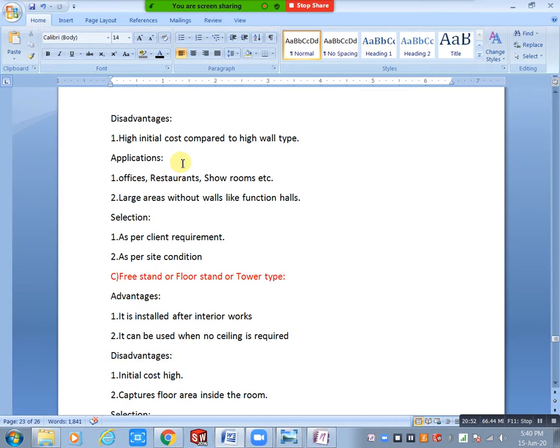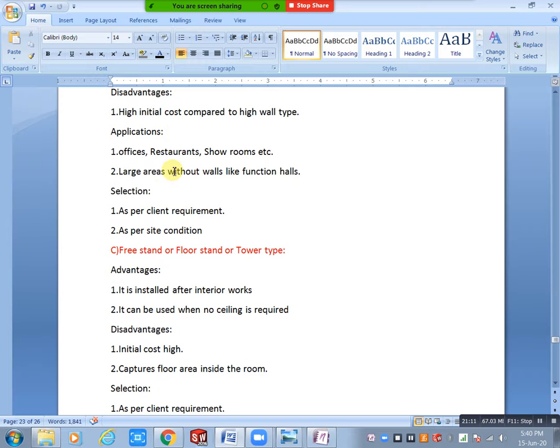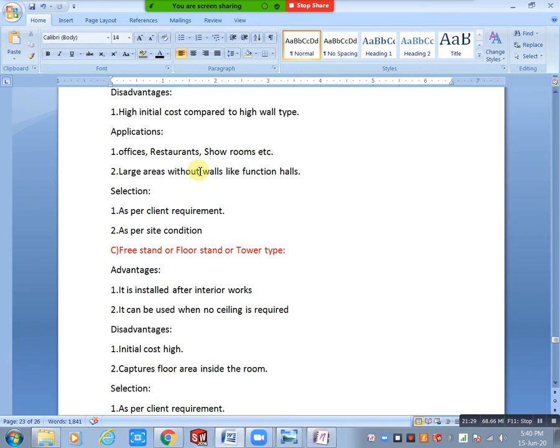To avoid bad smell, we need water seals and U-trap. After installing AC, within one or two months you will start getting bad smell — to avoid this, we need seals and U-trap. Cassette type disadvantages: high initial cost — approximately 20-30% higher than high wall type. Applications: offices, restaurants, showrooms, and large areas without walls like function halls.